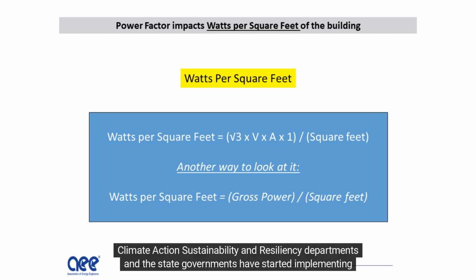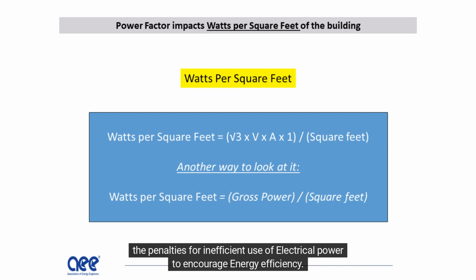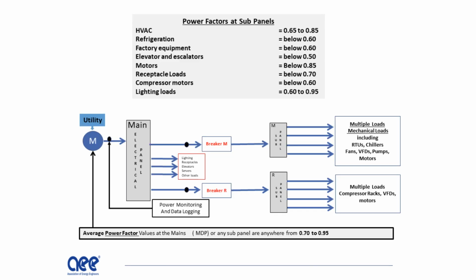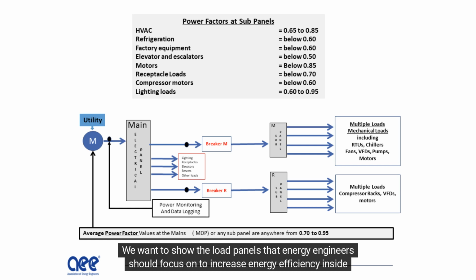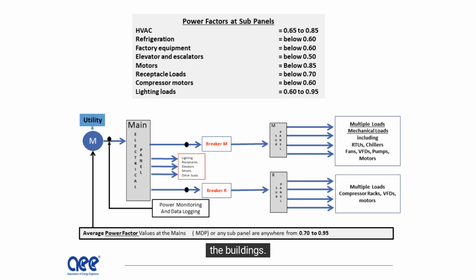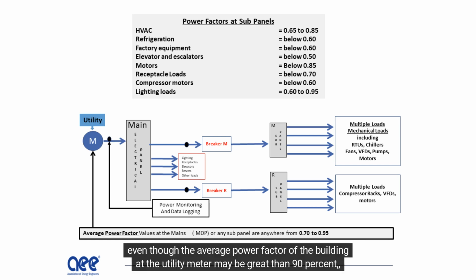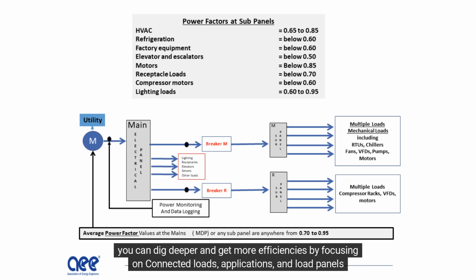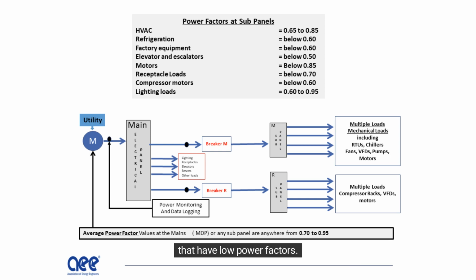Climate Action Sustainability and Resiliency departments and the state governments have started implementing the penalties for inefficient use of electrical power to encourage energy efficiency. We want to show the load panels that energy engineers should focus on to increase energy efficiency inside the buildings. Even though the average power factor of the building at the utility meter may be greater than 90%, you can dig deeper and get more efficiencies by focusing on connected loads, applications, and load panels that have low power factors.